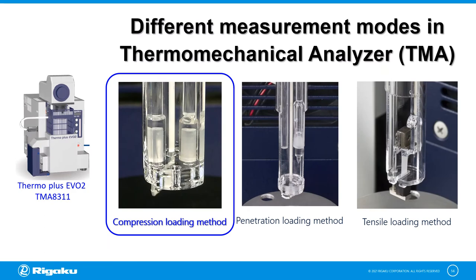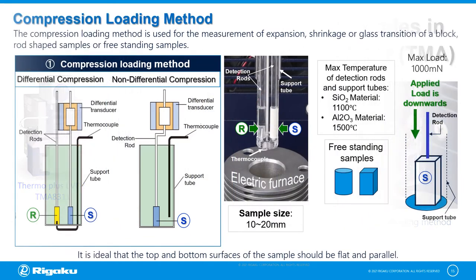In TMA, we have three basic measurement modes: compression loading method, penetration loading method, and tensile loading method. The compression loading method is used for the measurement of expansion, shrinkage, or glass transition of a block type, rod-shaped, or generally a free-standing material with 10 mm to 20 mm in length.